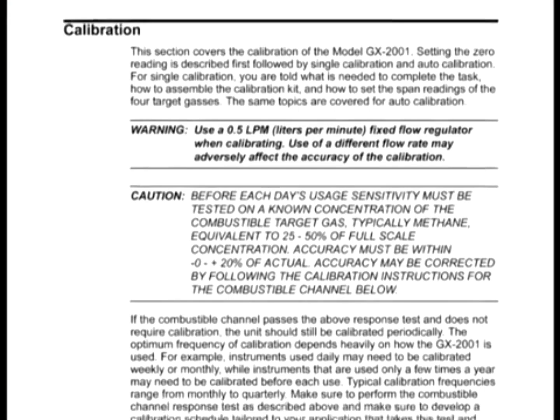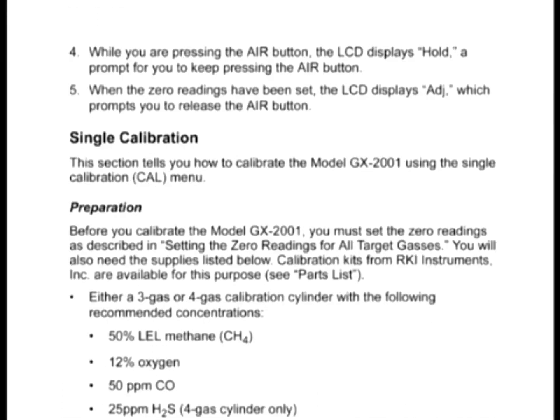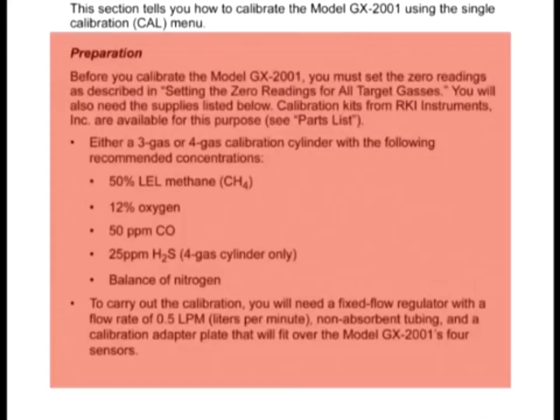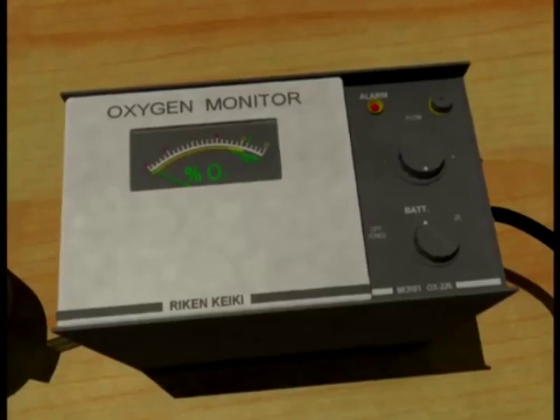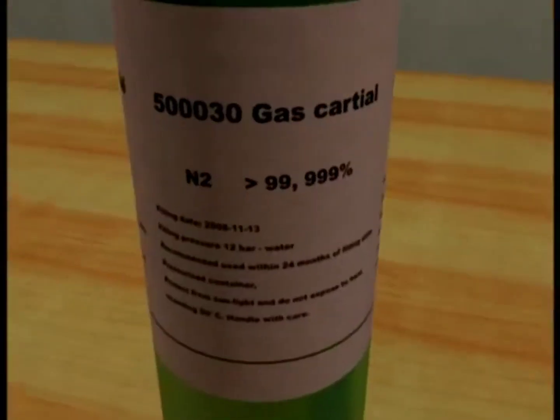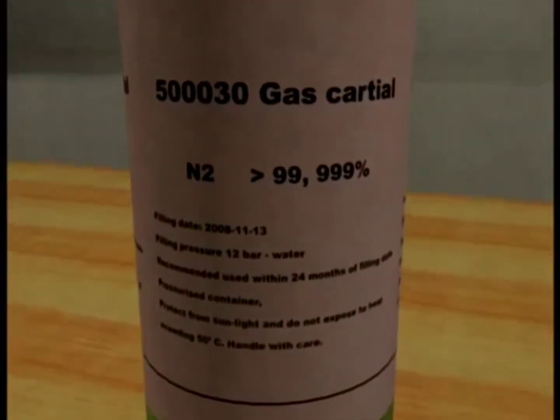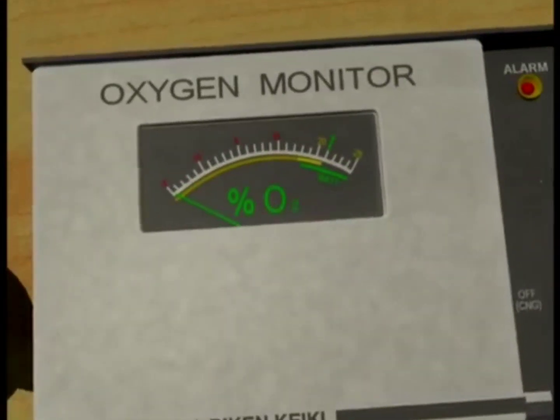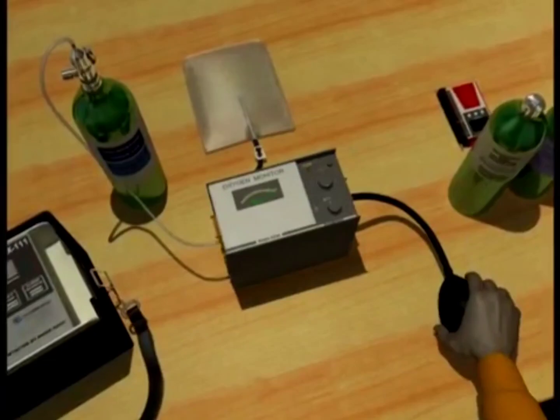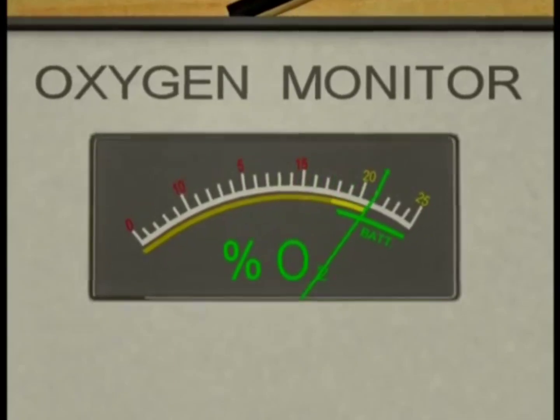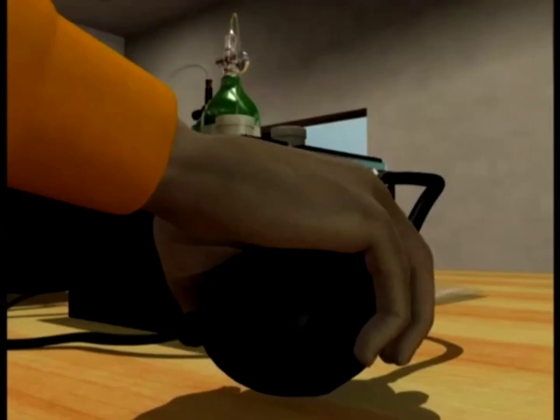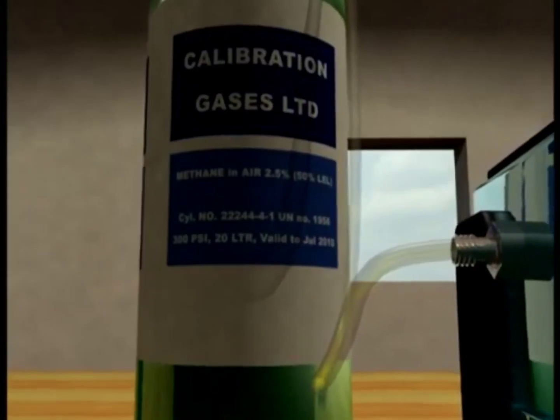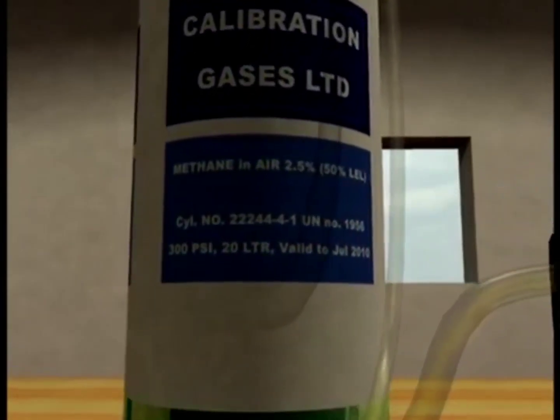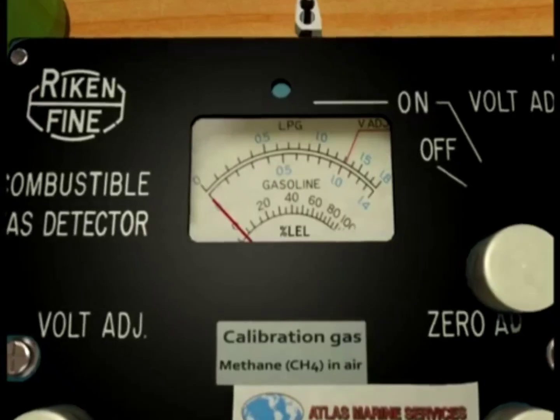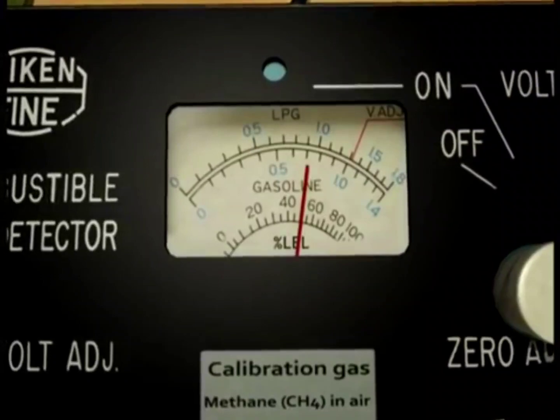It is important to use the correct span gas for the equipment to be calibrated. This can be determined from the instruction manual of the equipment. An oxygen detection meter is calibrated using 99.99% or more pure nitrogen to check for zero setting of the meter. The unit is calibrated for upper setting of 21% by aspirating the meter in air. A combustible gas meter or explosimeter is calibrated using methane in air mixture with 2.5% volume of methane and balance air. This will give a reading of 50% of LEL on the scale.